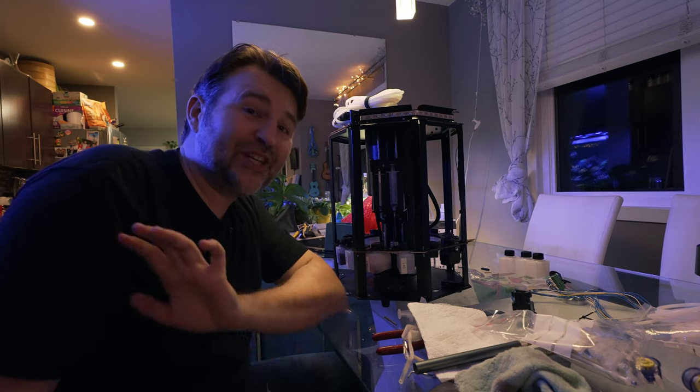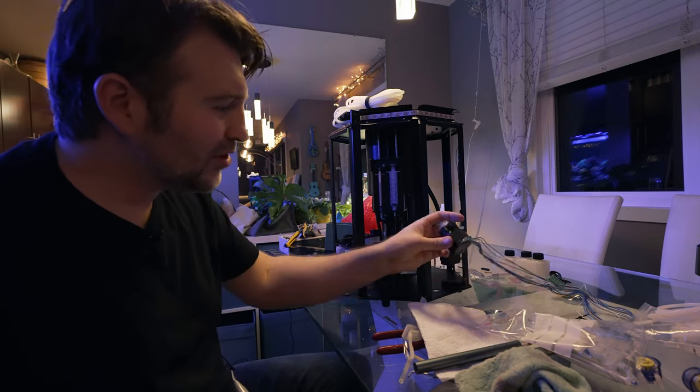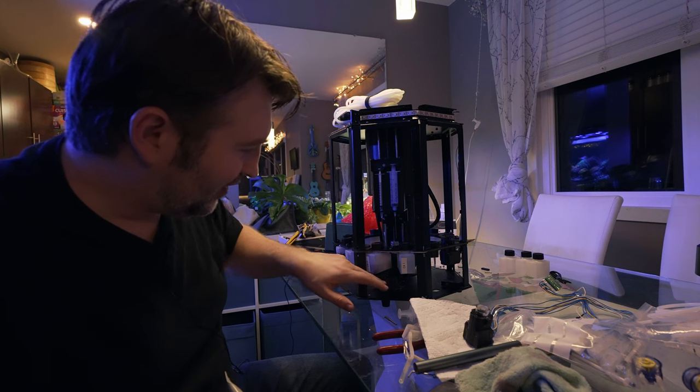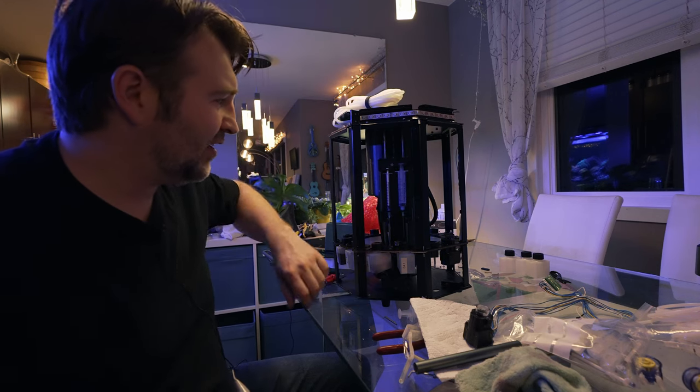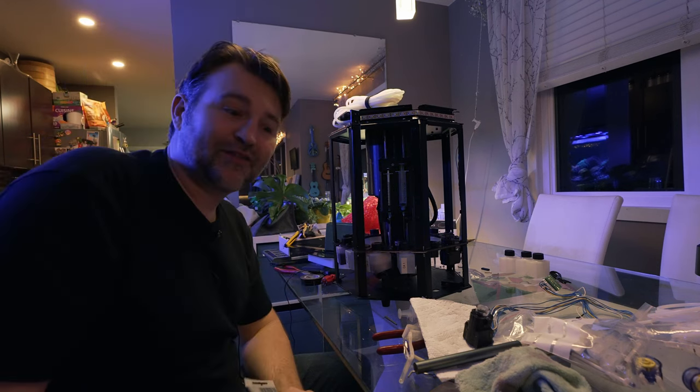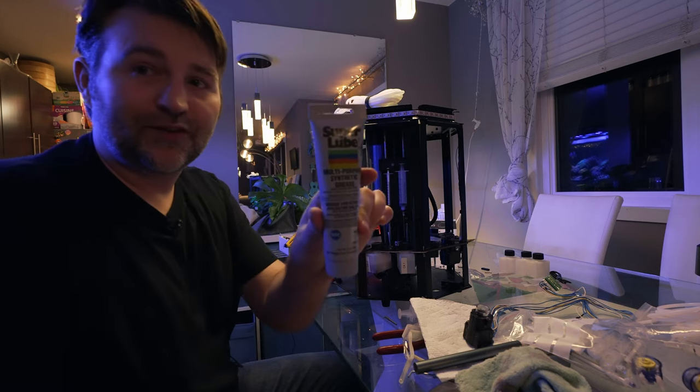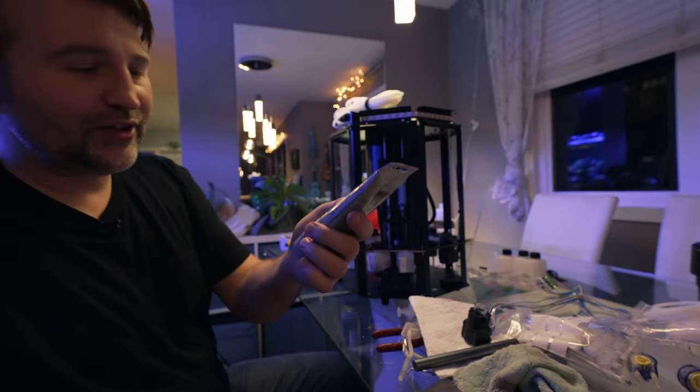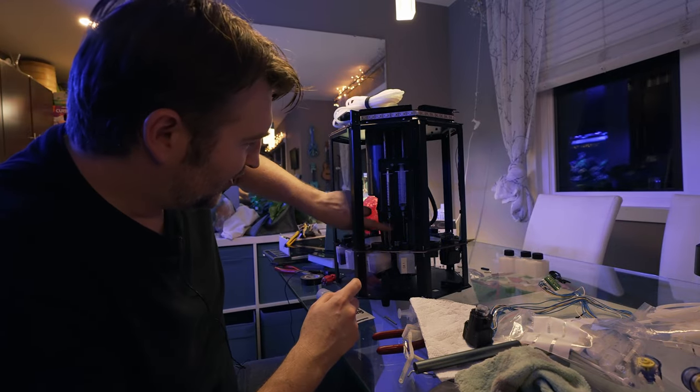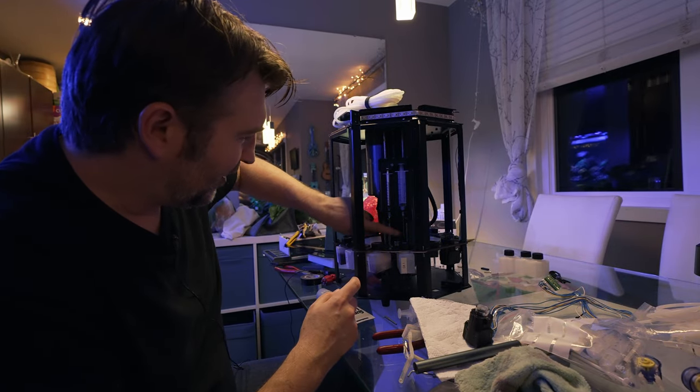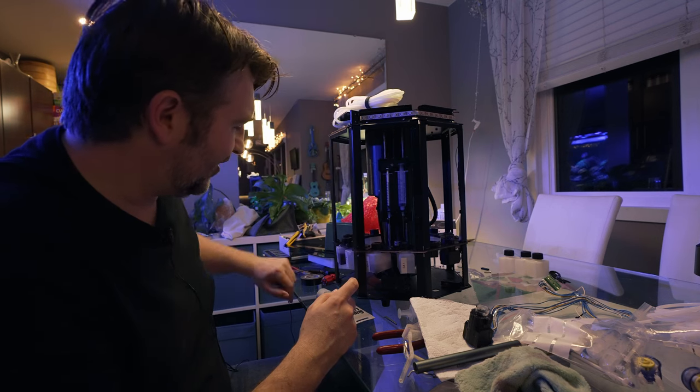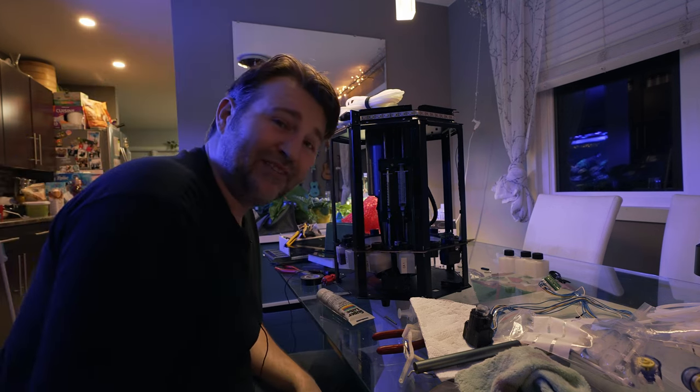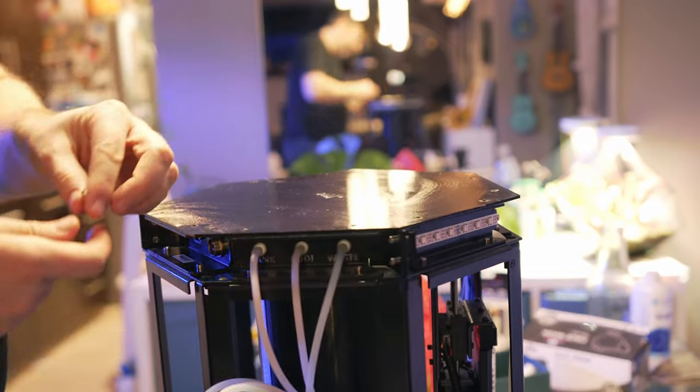And it is pretty much good as new. We replaced the colorimeter, we replaced the magnetic stir head, the tubing in it, the syringes and the needles. So everything's basically new. The only other last pro tip is use a bit of super lube. And this is something that I've used on my 3D printers on all the lead screws and it works very well. So put it on your finger and it's going to put on the rails and the screws and it will just make sure everything is lubricated so it slides nicely and stays nice and quiet. And the fun part, we're reinserting all of our screws.